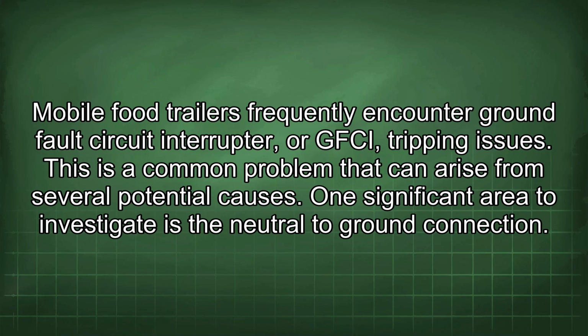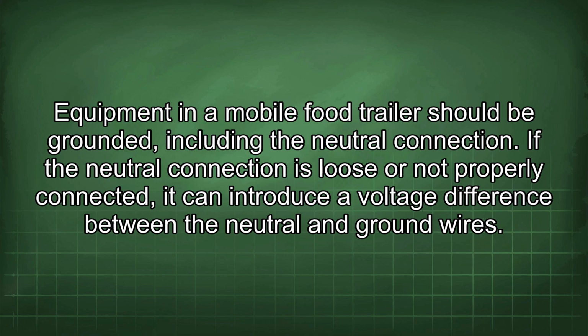Mobile food trailers frequently encounter ground fault circuit interrupter, or GFCI, tripping issues. This is a common problem that can arise from several potential causes. One significant area to investigate is the neutral to ground connection. Equipment in a mobile food trailer should be grounded, including the neutral connection.